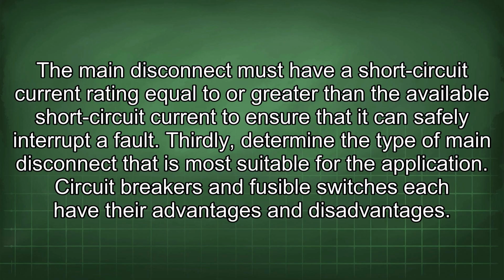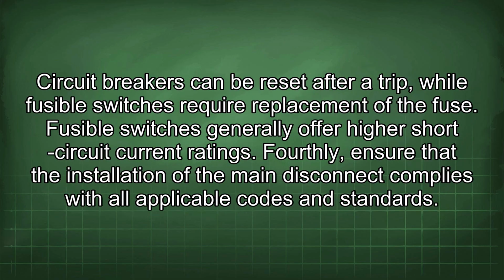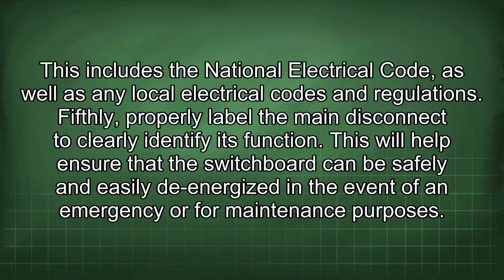Thirdly, determine the type of main disconnect that is most suitable for the application. Circuit breakers and fusible switches each have their advantages and disadvantages. Circuit breakers can be reset after a trip, while fusible switches require replacement of the fuse. Fusible switches generally offer higher short-circuit current ratings. Fourthly, ensure that the installation of the main disconnect complies with all applicable codes and standards. This includes the National Electrical Code, as well as any local electrical codes and regulations.